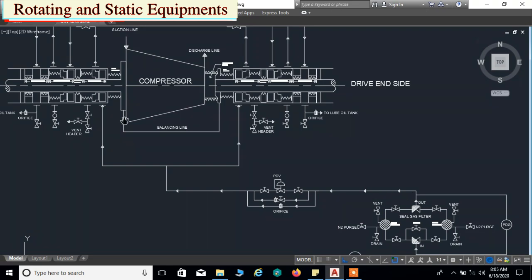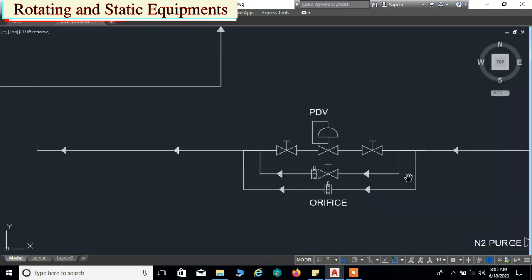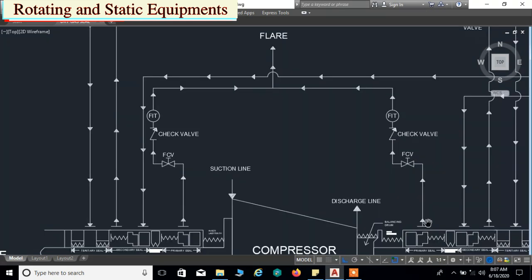Cleaned seal gas is injected to the primary seals on the drive end and non-drive end sides through an orifice. The seal gas pressure is controlled and maintained by a pressure differential control valve. The seal gas returned from the primary seal chambers is sent directly to the flare system to be burned, through a flow control valve and flow orifice valve, by means of lines called primary venting lines. A differential pressure transmitter installed between the upstream and downstream of the flow control valves provides alarm signals and trips the unit in case of high pressure.